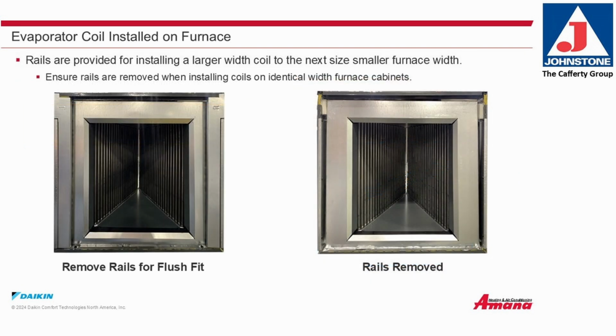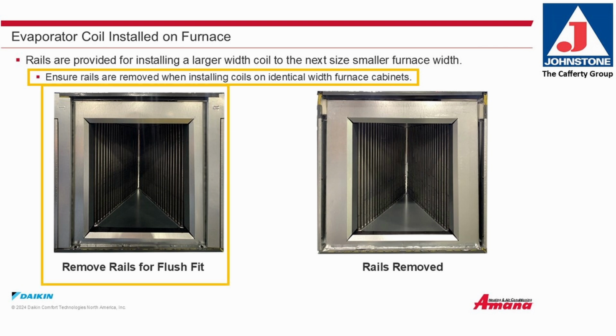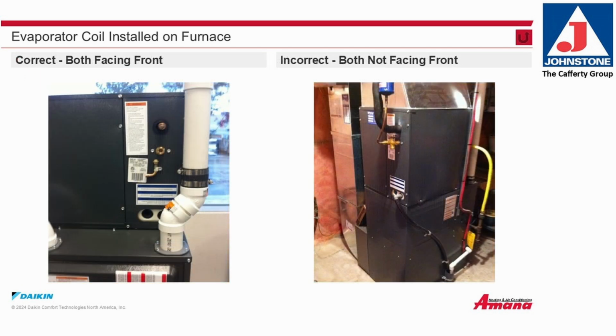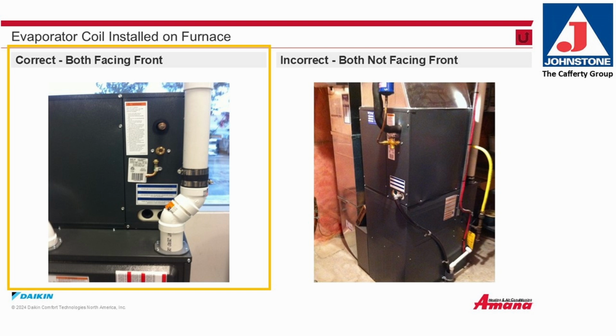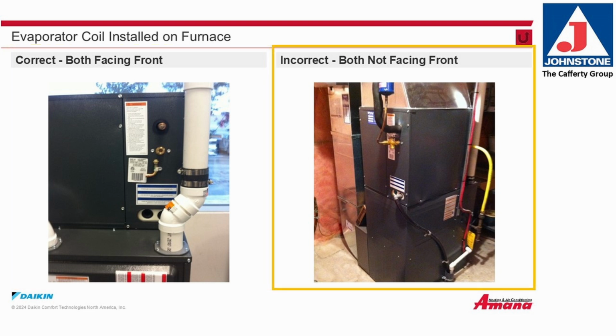Evaporator coil installed on furnace. Rails are provided for installing a larger width coil on the next size smaller furnace width. Ensure the rails are removed when installing coils on identical width furnace cabinets. Here is an example of the bottom of the coil cabinet with the rails installed and the rails removed. Correct is both facing front. Incorrect is anything other than both facing front.